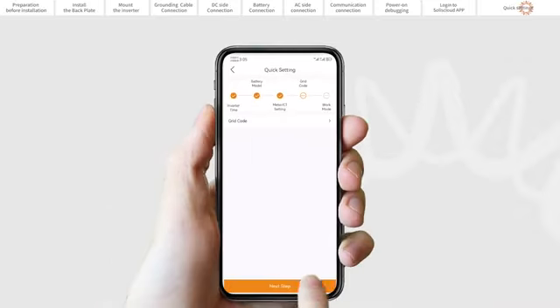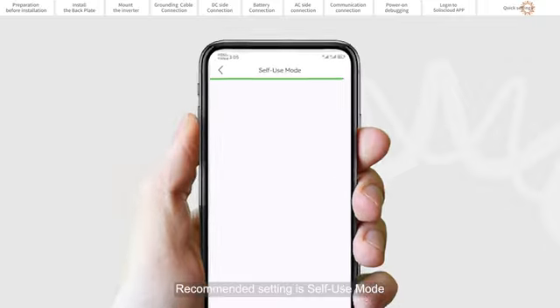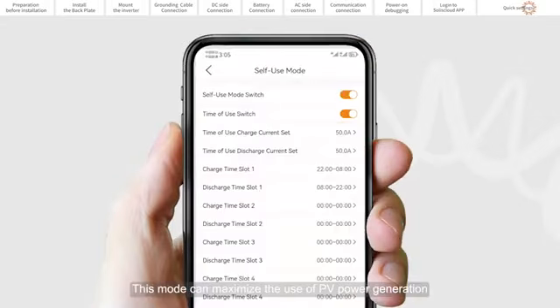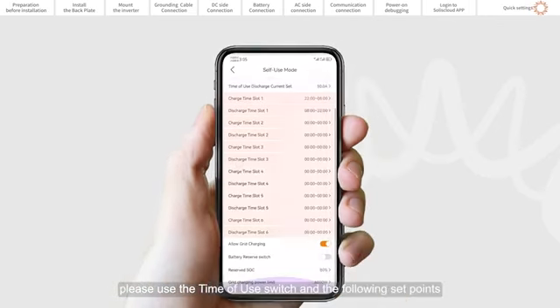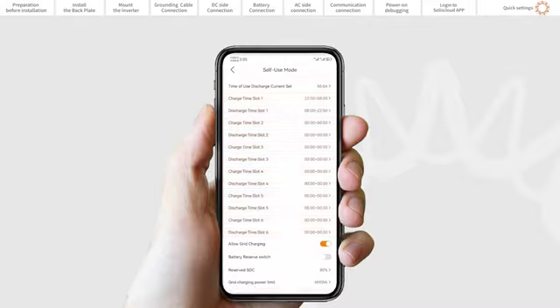Set the work mode. We recommend setting to self-use mode. This mode can maximize the use of PV power generation for household electricity, or store it in the batteries and use it for household electricity. If needed, manually control the battery charging and discharging with respect to time. Please use the time of use switch and the following set points as required. Allow grid charging is recommended to be turned on.